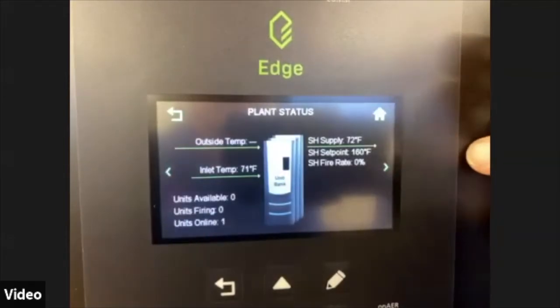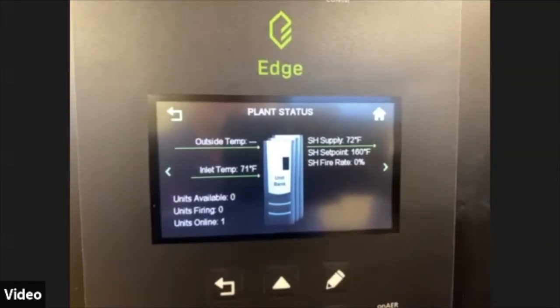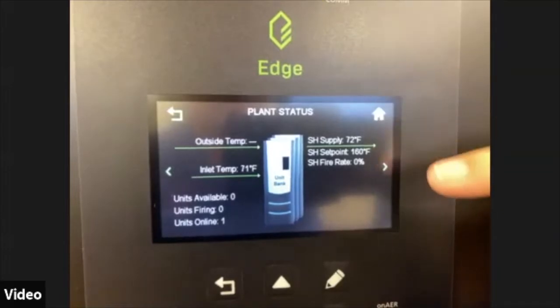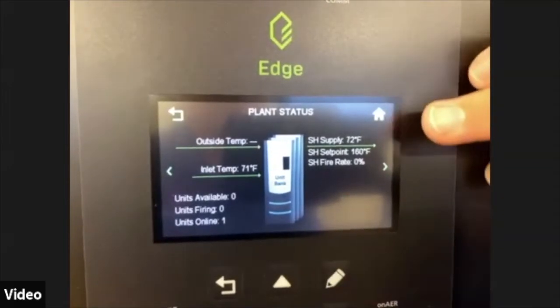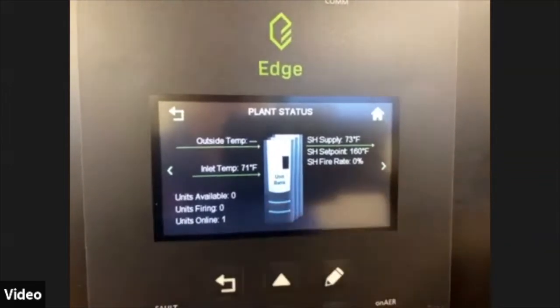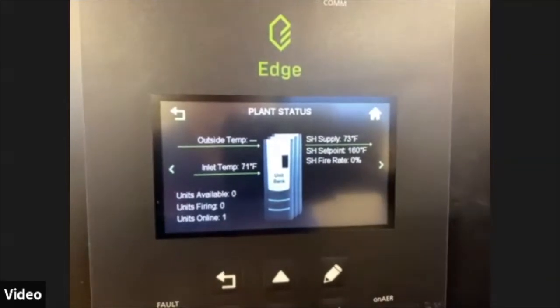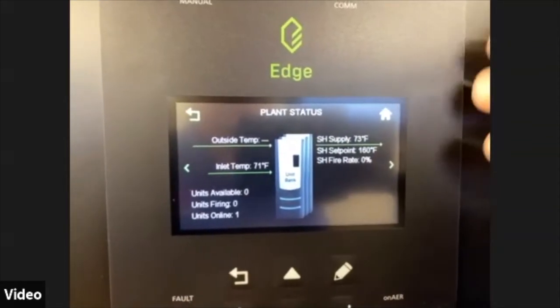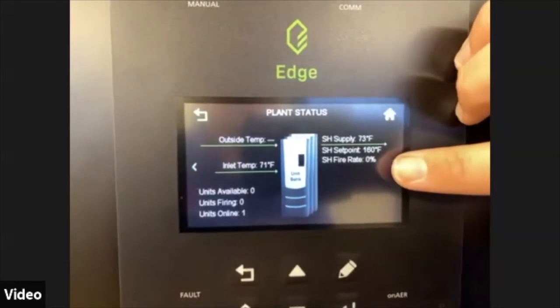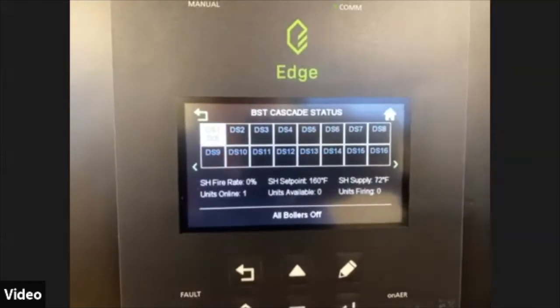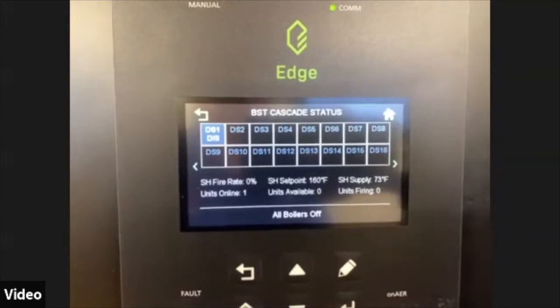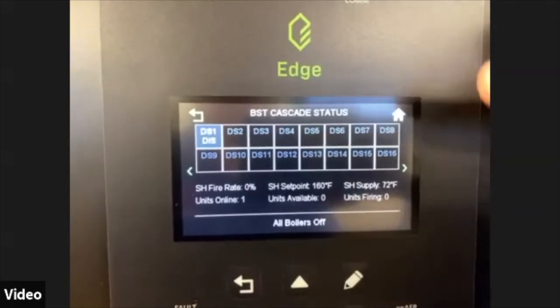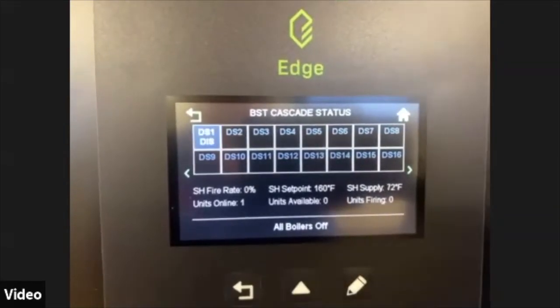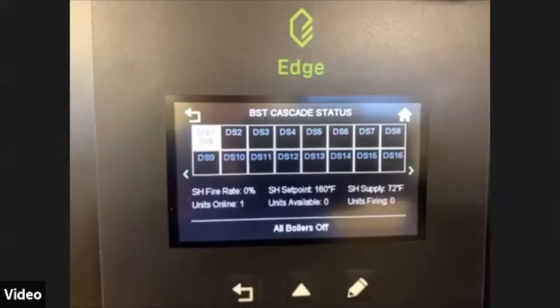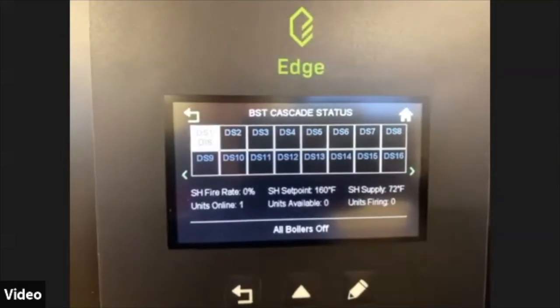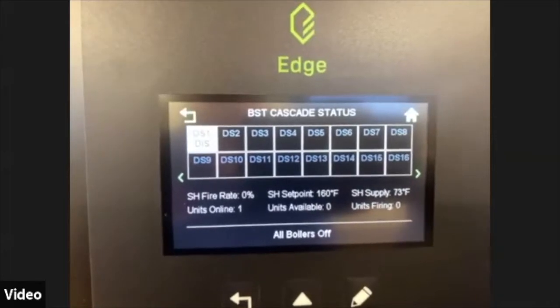If you go right, that's going to show you your plant status. So if you have multiple boilers, it gives you all that pertinent information. It gives you how many units are available, how many units are firing, just tells you what the whole boiler plant is doing. Go to the right again, this is where it gives us our BST Cascade status. Like I said, it can do up to 16 boilers, and if we had boilers wired in, they'd all be flashing like this. Obviously, this boiler we have disabled because it cannot fire in our training room.